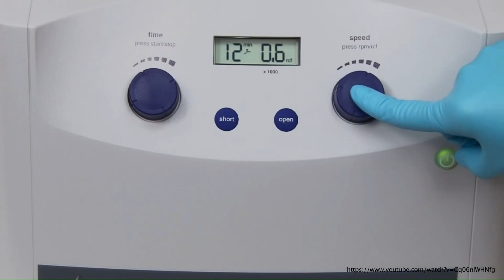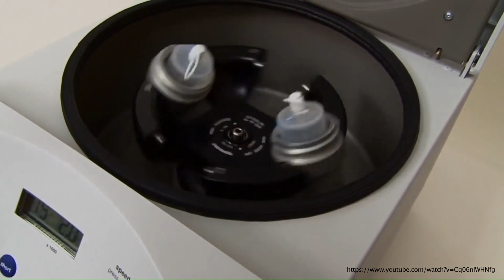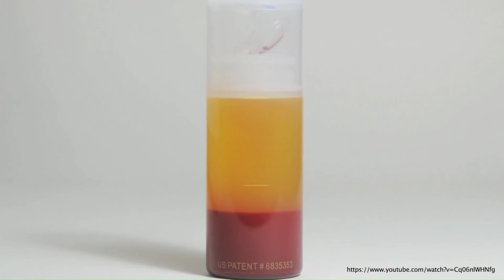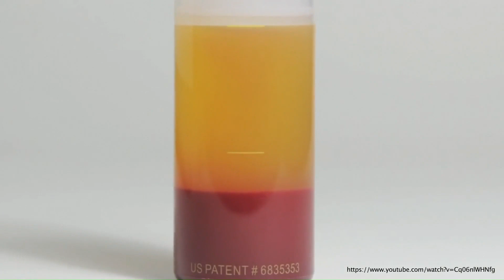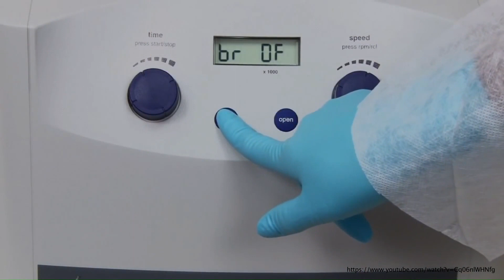To the right, you will find the speed button, which can also be turned to set the RPM speed, and pressed to toggle between the RCF and RPM display. These buttons are clear and easy to operate. The centrifuge comes with a controlled deceleration and soft braking feature. This minimizes cell agitation and resuspension during processing. Optimized separation is achieved without agitation, providing the best achievable cell concentration for your procedure. To activate this feature, press and hold the short button until you see BR off indicated on the display.